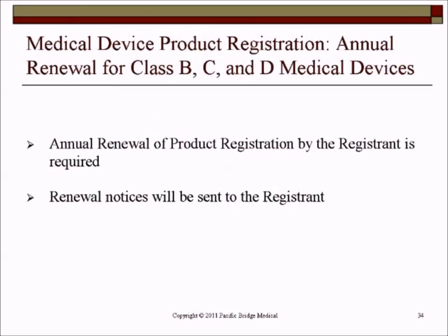The annual renewal of the product registration is also done online, and HSA would provide a renewal notice to the registrant about 30 days before the license expires. At this point, you basically need to go into the system, provide any changes to the products if needed, make a declaration on the system, and pay the necessary fees, and the product gets registered. So you do not need to submit any new technical information for this, provided that all the intended users and indications for use are the same.